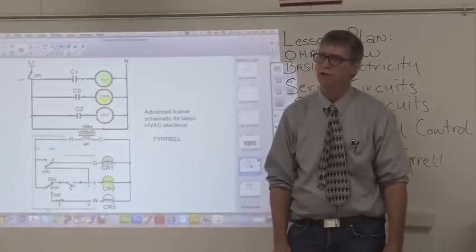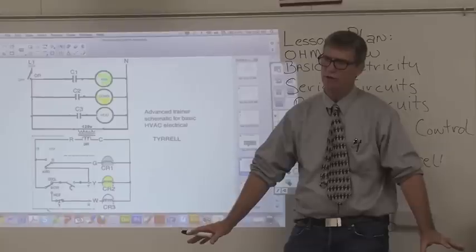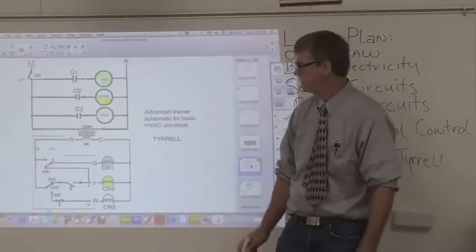When we run it through that switch, we're going to bring hot down to one side of the primary transformer and neutral to the other side. That is going to power the transformer, and on the secondary side, it's going to step the voltage down to 24 volts AC. We're not using DC voltage at all — this is 24 volt AC.